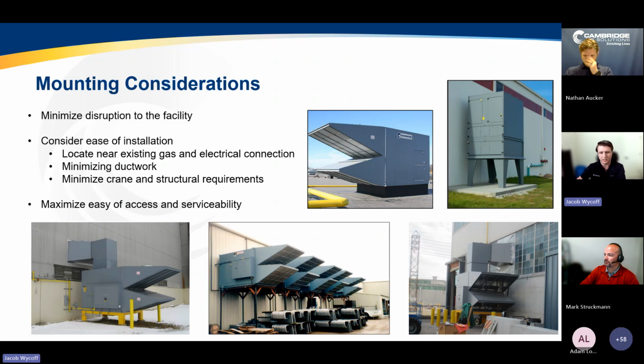We also see in these industrial retrofit opportunities, mounting the units outside on a stand or a pad, or as a vertical unit on some legs, in order to minimize the crane requirements. It's going to require a much smaller piece of rigging equipment like a crane to set a unit down on the ground on a pad as opposed to setting it up on a roof. And in many cases, these industrial facilities that have been designed for 50-plus years don't have the roof design to support structural HVAC equipment. So it would require a lot of reinforcement to set HVAC equipment on the roof. That's why in most of these industrial retrofit applications, we're seeing the unit on a pad just outside the facility and immediately ducted in, having that air thrown across the space.